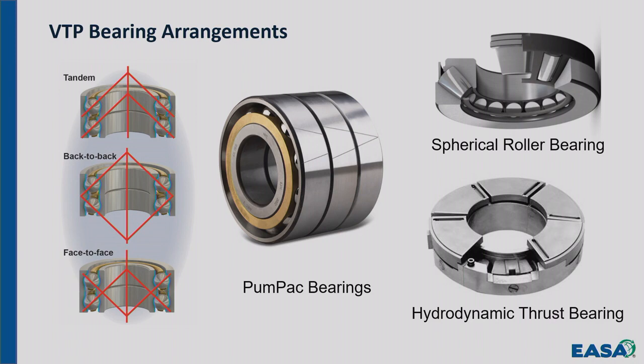And they can be configured different ways, some for up thrust, some for down thrust, face to face, back to back. There are spherical roller bearings that can be mounted on springs. Okay? In addition to the spherical roller bearing, sometimes you'll have the spherical roller bearing along with a ball bearing, where the spherical roller bearing takes the axial thrust and the ball bearing maintains the radial concentricity. Okay? There's a thing called a PumPac bearing, where you have two down and one up with different contact angles.